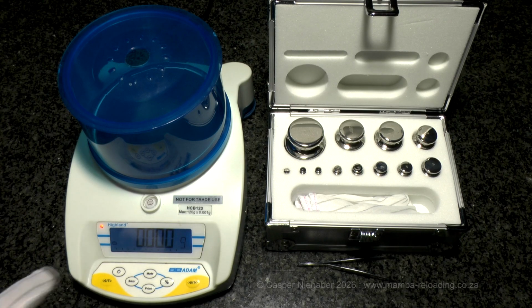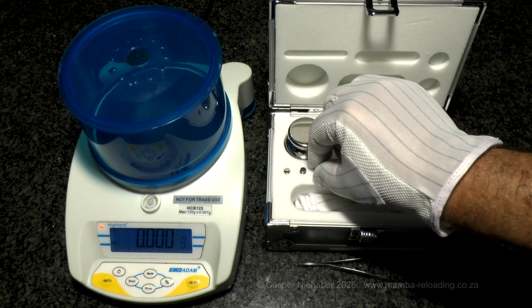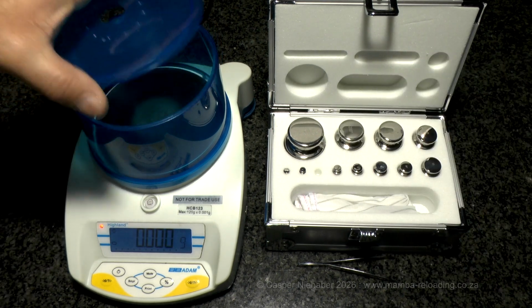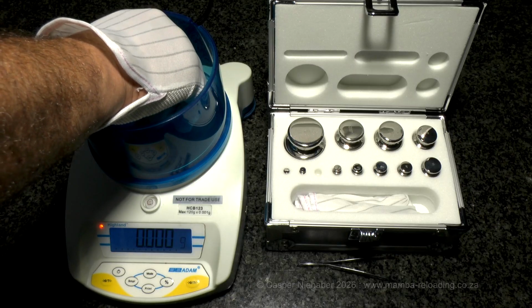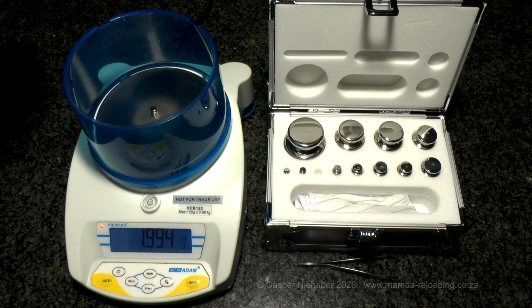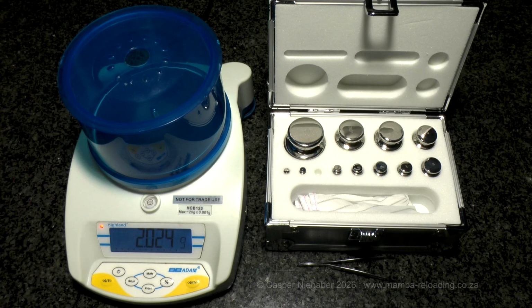Press the yellow Zero/Tare button to zero the balance. Remove the 2 gram test weight. Open the draft shield, place the weight in the center of the pan, and close the shield. The balance correctly displays 2 grams.